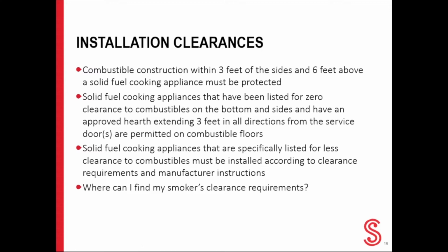Combustible construction within 3 feet of the sides or 6 feet above solid fuel cooking appliances must be protected in a manner acceptable to the authority having jurisdiction. This means appliances should be installed where there is at least 3 feet of space between the appliance and any combustible walls and 6 feet above the appliance and any combustible ceiling.